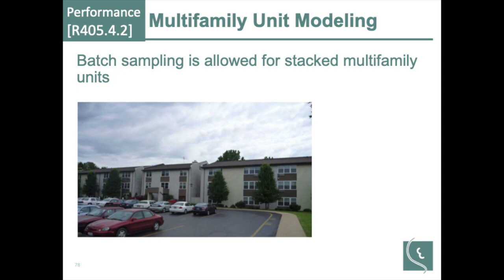The reason being is when you get into smaller units, well, your volume to surface area ratio gets out of whack. And really, what is the objective here? We want a tight envelope. Well, if I make a really big house with a relatively small envelope, my envelope can leak a lot. So they're saying we want you to test and prove a tight envelope, not just that it didn't leak so much volume.